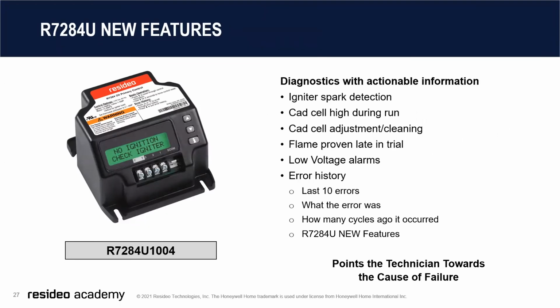As you can see, it has a little display on there. So it's going to actually have a variety of information available to you, both as diagnostic and as a more intuitive menu to navigate as you're setting it up. It's going to be able to tell you if the igniter has spark detection. It's going to tell you if the CAD cell is running high. It's going to tell you if it thinks the CAD cell needs adjustment or cleaning. If flame is being proven late in a trial, it's going to have a variety of low voltage alarms, error history. It's going to show the last 10 errors, what the error was, how many cycles ago it occurred. It's a pretty comprehensive tool for helping technicians diagnose the application.